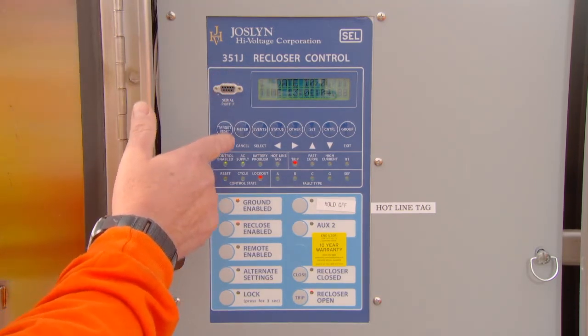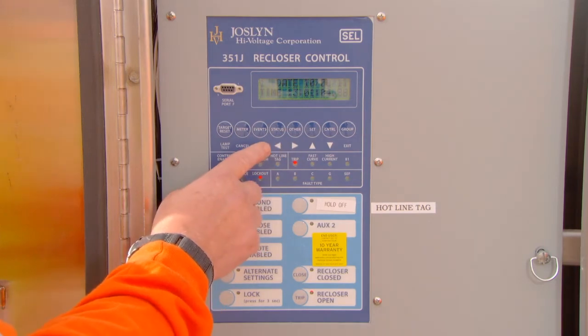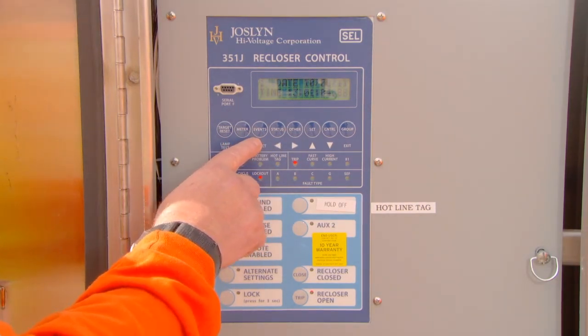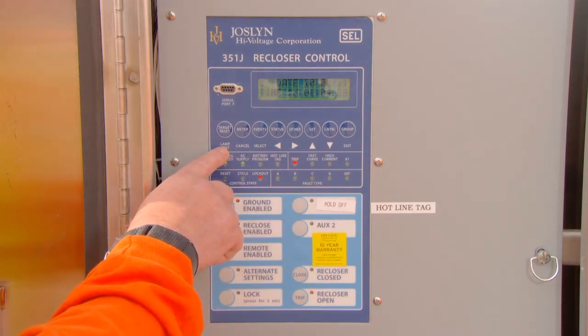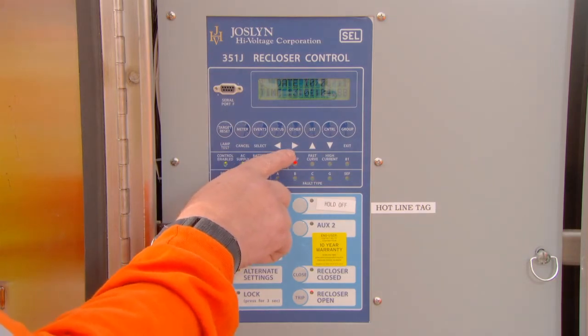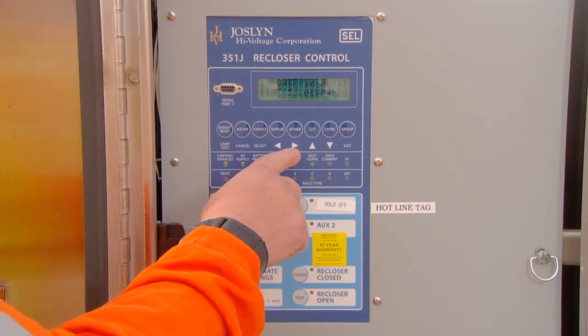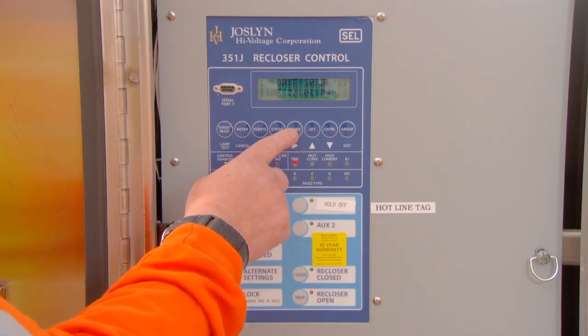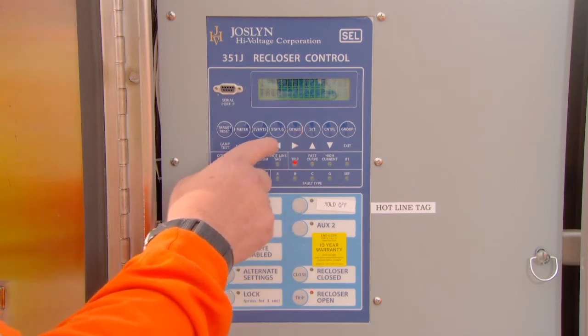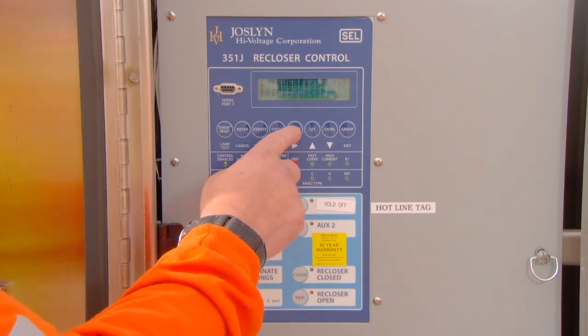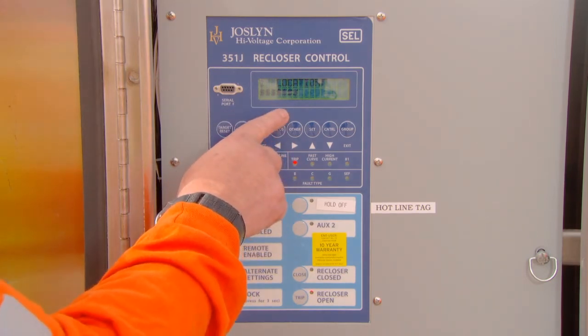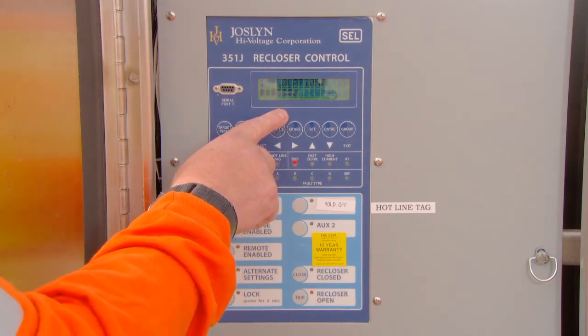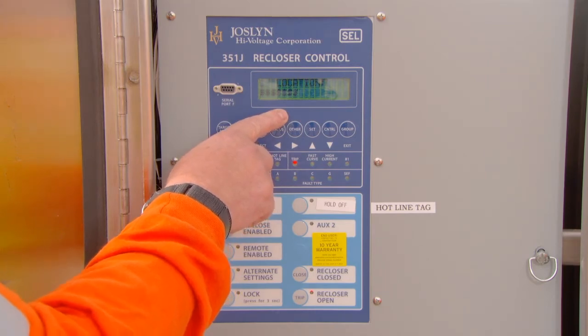After pressing any of these selection buttons for the first time, the second row of symbols below those selection buttons redefine the function of the buttons directly above each symbol. For example, pressing the Other button at this point will cause it to act as a redefined right arrow. The display will now scroll across to the right, showing us the fault information, which in this case tells us that it was tripped. Press the Other button again for it to function as the right arrow button. The control will only display the actual fault location if you have both voltage and current supplies, and it is programmed for this function. Otherwise, what will be displayed will be dollar signs.